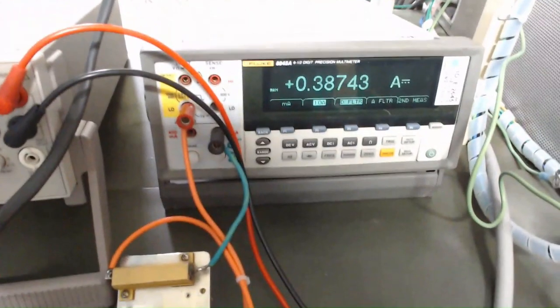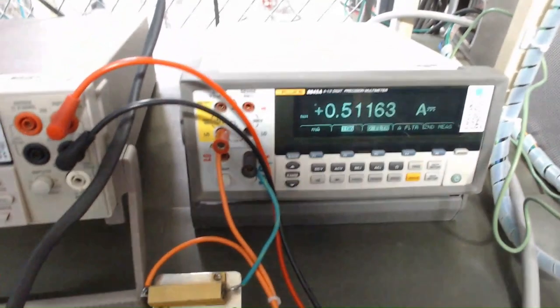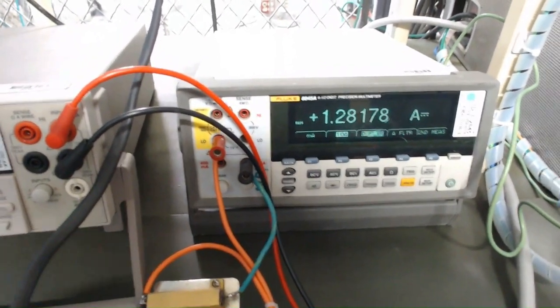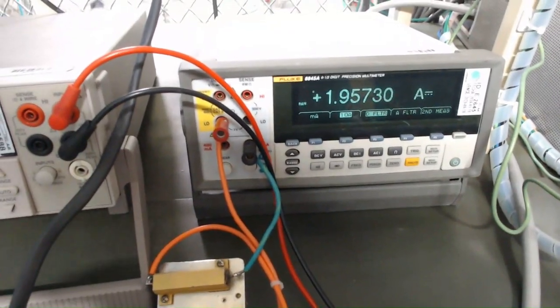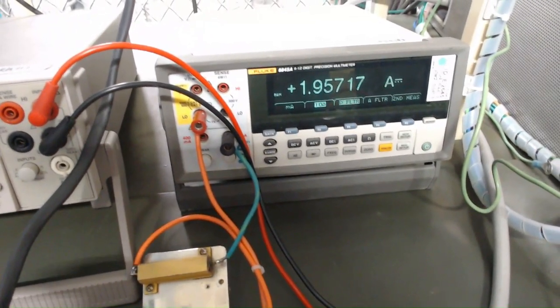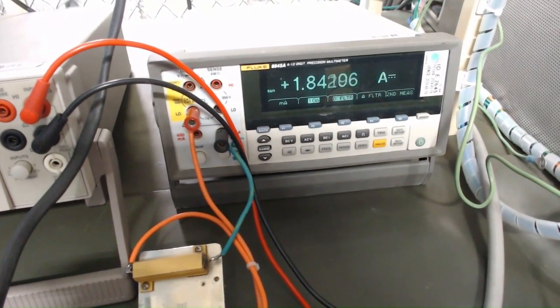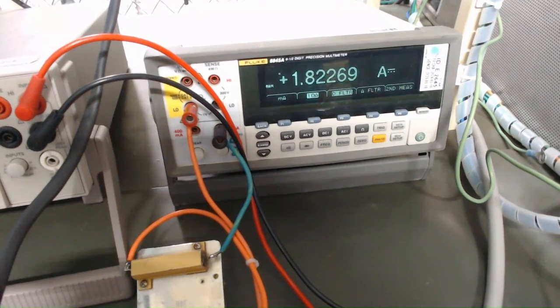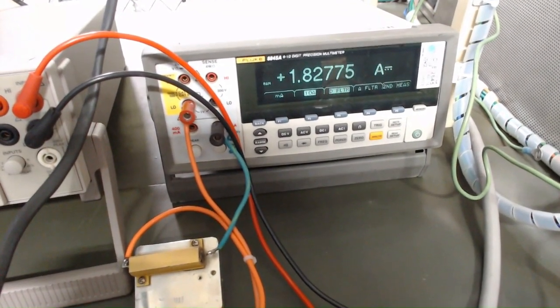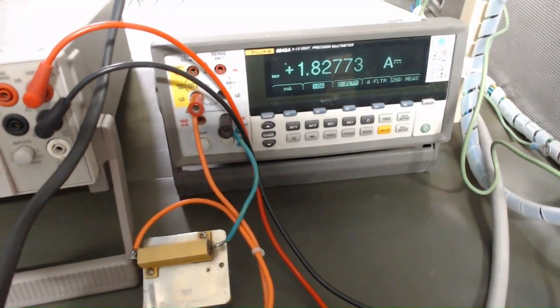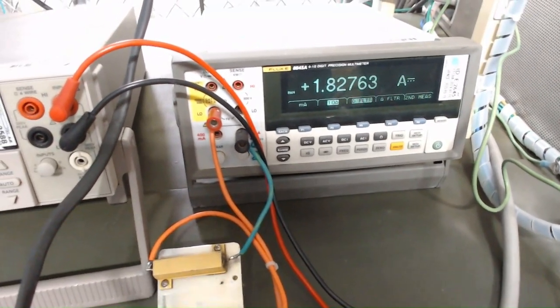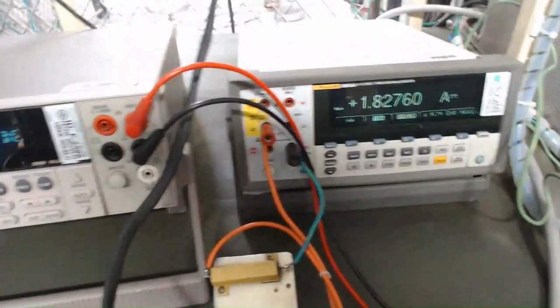We will then proceed to close the interlock and adjust the filament limit potentiometer between minimum and maximum. Values should be able to be adjusted between 0.5 amps and 1.8 amps. As with the preheat values, these are expected to be able to be adjusted slightly lower than 0.5 amps and slightly higher than 1.8 amps to provide adjustment margin. At this stage, after confirming the range, is where the filament presets will be carried. However, since X6417 does not have any preset specification, potentiometers would be set to minimum after the filament voltage limit test.